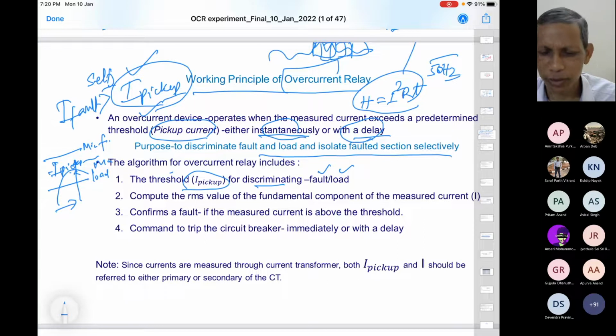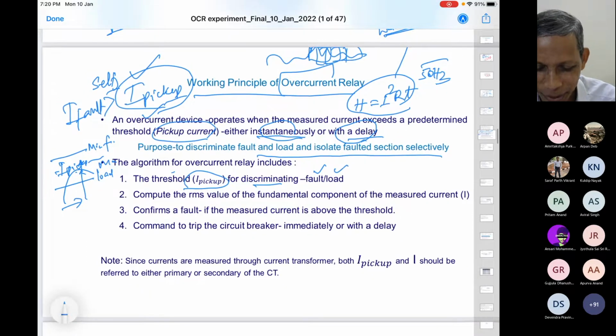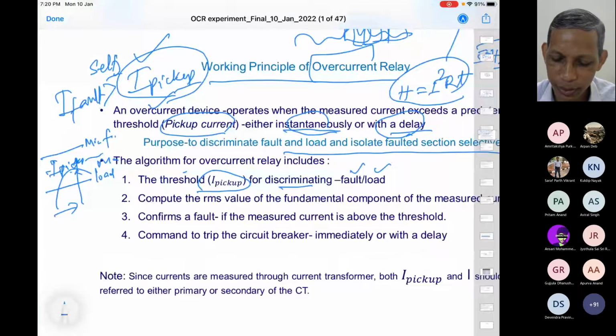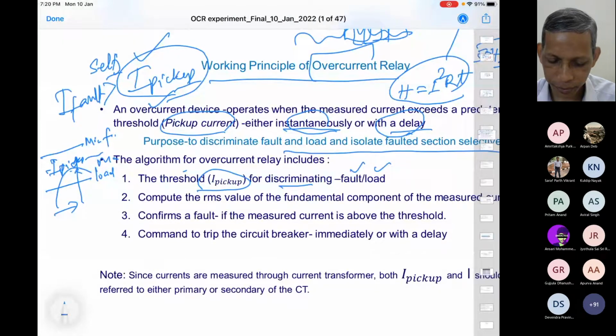Is it a fault? No. It's normal operation. Like the inrush current I told you about: when a transformer downstream is switched on, inrush current will flow, and in the upstream the relays will see that the currents are high. They should not trip. They should wait and watch. So that's the point. Accordingly, the pickup setting is chosen, and then the time should be there.